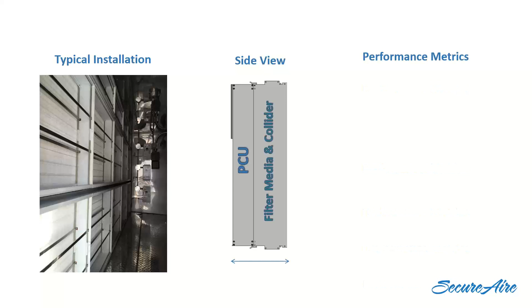So they test this filter as an assembly, the charging mechanism and the filter media itself, and it's rated for Merv 15. Right? And if you remember, the scale goes from 1 to 16, and then after that you'd be in HEPA land. So it's one notch below the top Merv rating that they could have gotten. It doesn't have very much pressure drop, 0.28 inches. That's pretty low, compared to most systems like at a hospital, and compared to a HEPA that might have 1 or 1.5 inches of static pressure drop. So that means it doesn't take a lot of fan energy to do this, as compared to other technologies that get you a Merv 15.